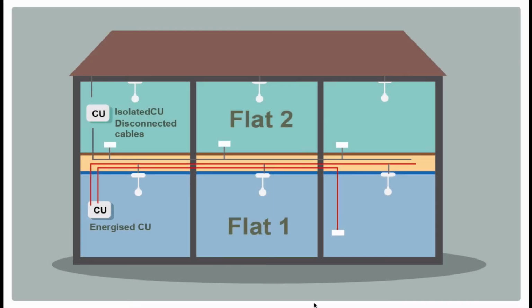I mentioned that I like to strip all the cables out of the fuse board, so I know that there's nothing energized within the flat, and it's just the temporary sockets. Every other circuit's gone now, so people can work safely. And we're talking about a 3-bedroom house, but you could be working in a flat. Now, the downstairs flat, that's still all energized. The upstairs flat, you've ripped everything out of the fuse board, so you think everything's dead.